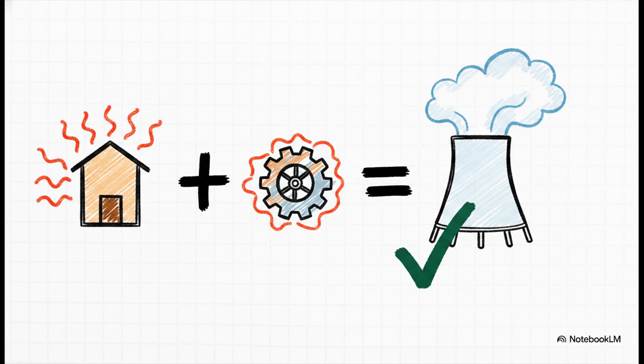But let's be real, relying on old-school historical units like refrigeration tons and trying to remember safety multipliers is pretty clunky for modern engineering. So the industry has a brilliant solution. We're transitioning to universal metric units like kilowatts or kilocalories per hour to completely eliminate these mathematical mix-ups. By mapping out pure physical heat energy in kilowatts, an engineer can just look at a spreadsheet and see it clearly. The room produces 350 kilowatts of heat, the compressor produces 100, so boom, the roof absolutely needs a minimum of 450 kilowatts of exhaust power. No historical confusion, just pure, undeniable physics, perfectly mapped out.